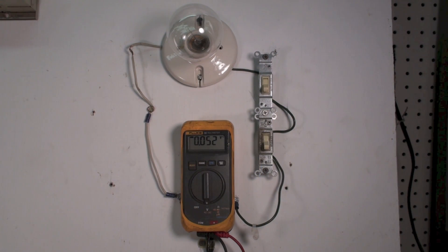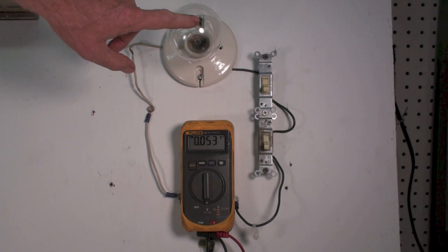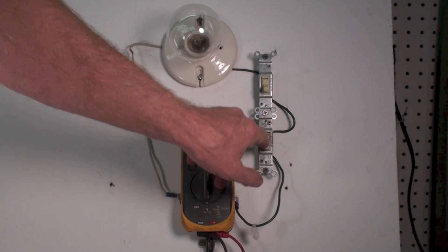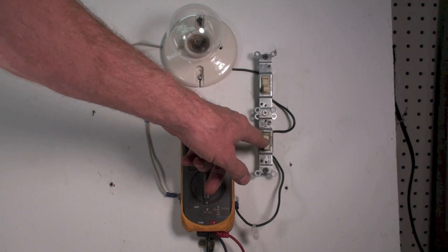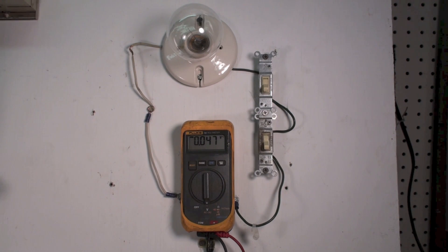Okay, this is the next in the series of using the voltmeter to troubleshoot. Now you may notice I've got my load just like I had it before. I've got two switches and the two switches are in series. Series simply means if I shut one switch off it shuts it off. If I shut both switches off it's already shut off, so it's not going to make any difference. So one of those switches off and the unit won't work.